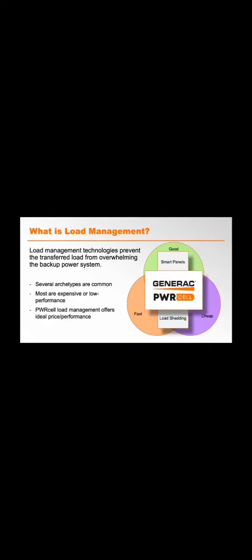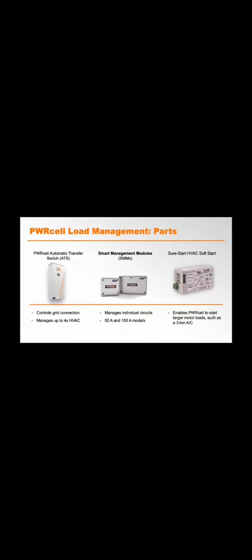GENERAC has a third option available. It's cheaper and easier than a smart panel, and it's much smarter than load shedding. So let's check it out. Here are some of the components that we use in our load management system. We're not going to take a terribly deep dive on any of them, but I do want you to be familiar with each component just generally. The PWRcell ATS is what islands the system in a whole home configuration. This is what we saw earlier. Basically, it breaks the connection to the network when the grid goes down so that all of the solar and battery energy stays on premises.